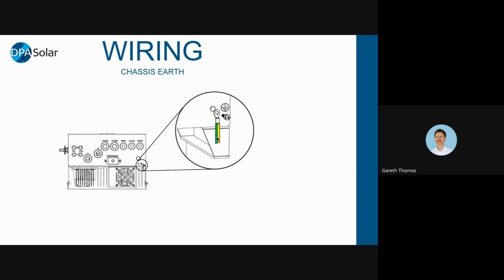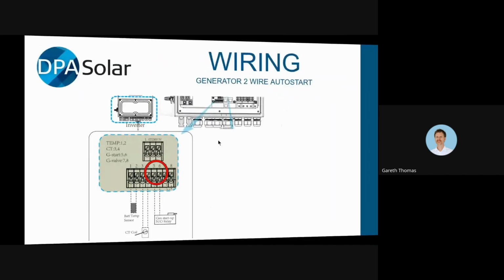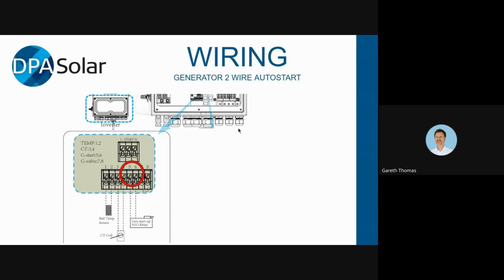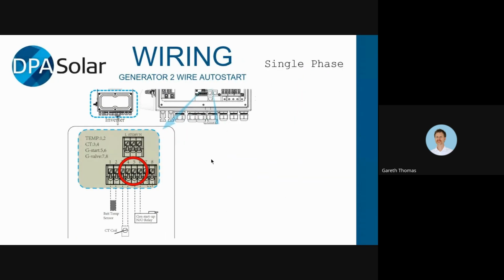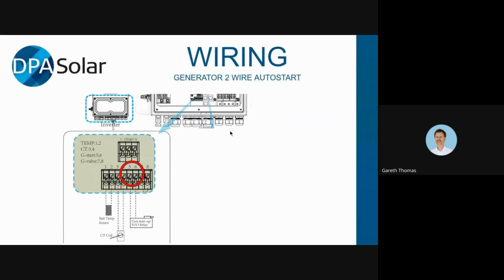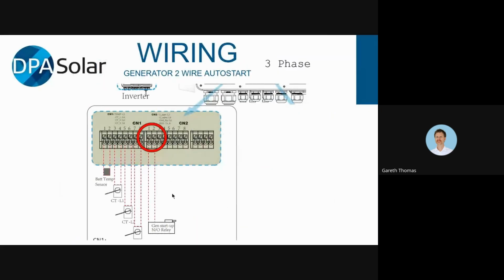Then there's a chassis earth that needs to be connected as well. It has a generator 2-wire auto start function built into it. On the single phase, that goes to pins 5 and 6. It's just a dry contact. There's no voltage on it. And for the 3-phase 2-wire auto start, it's just on pins 1 and 2 on the second row. All of this is in the manual.